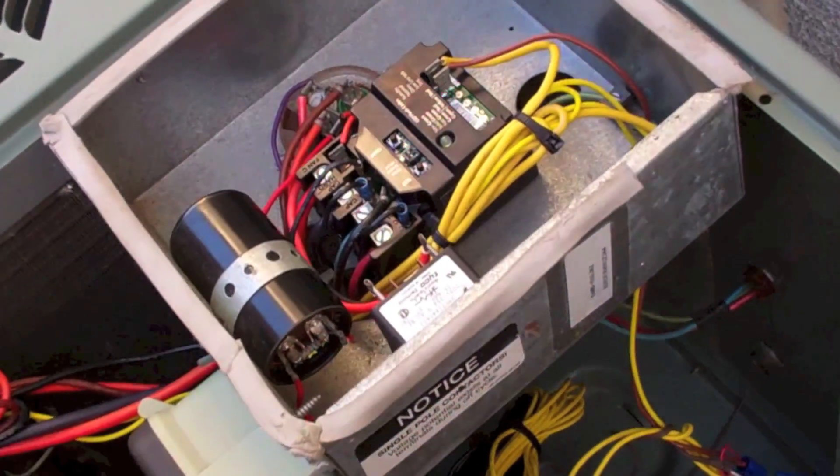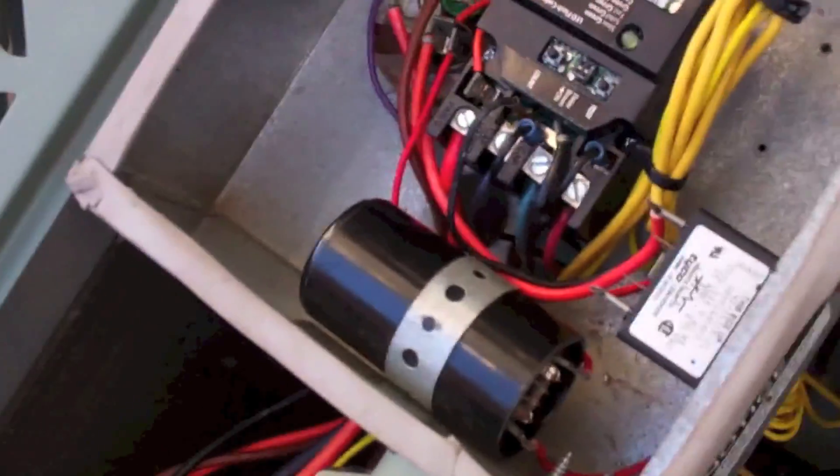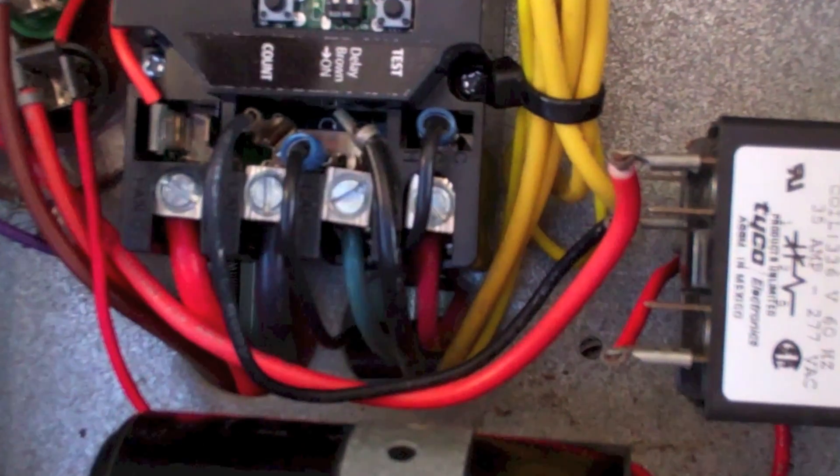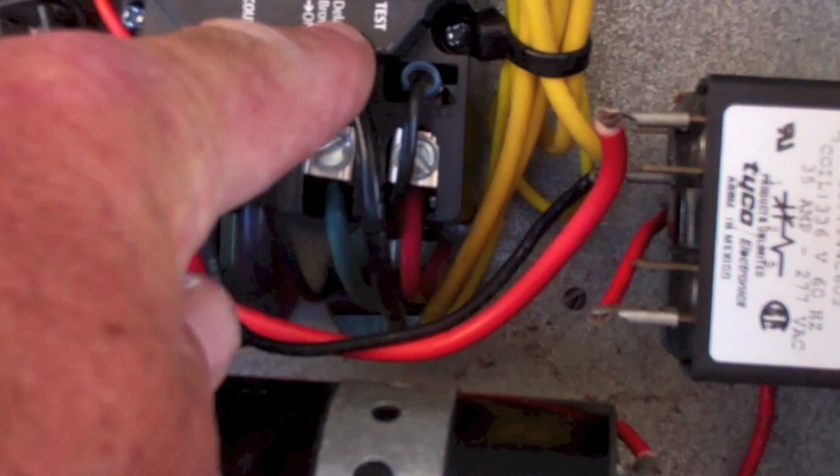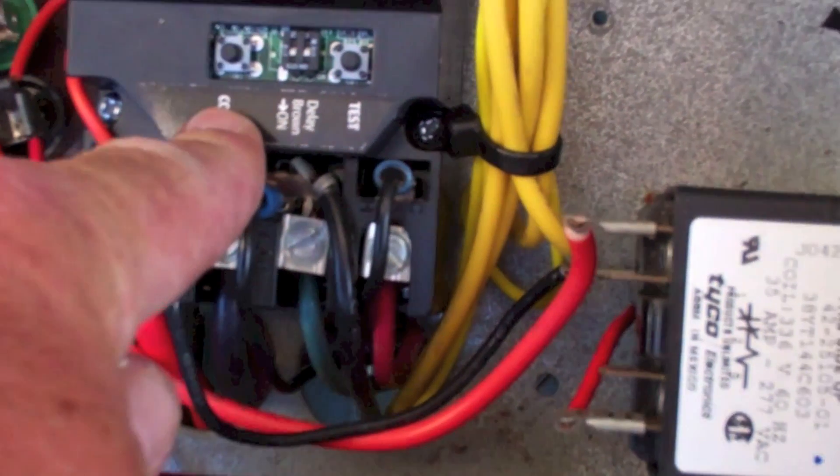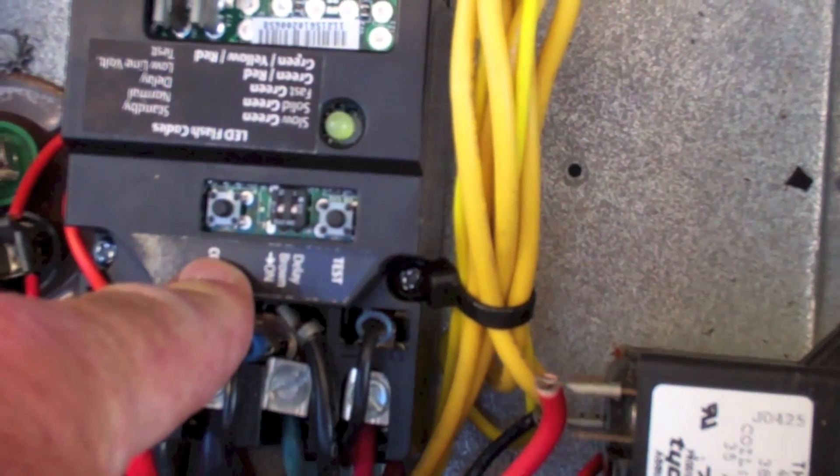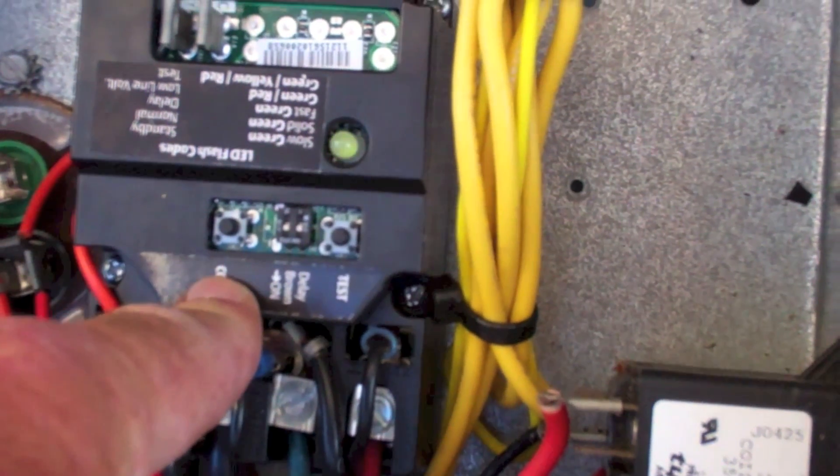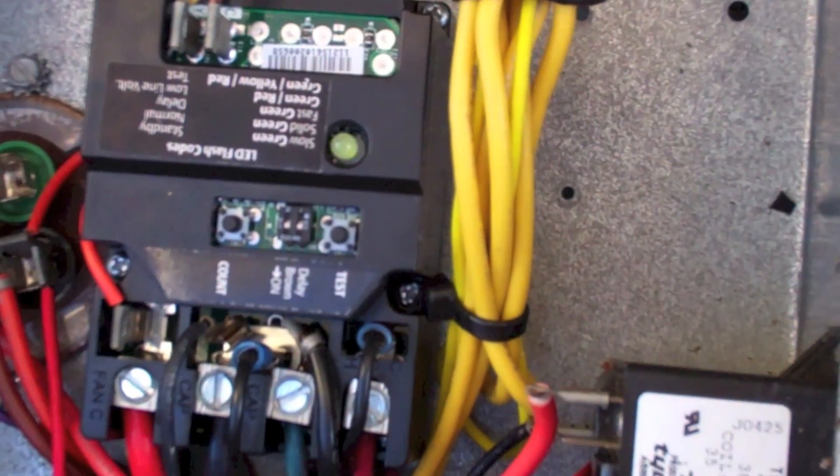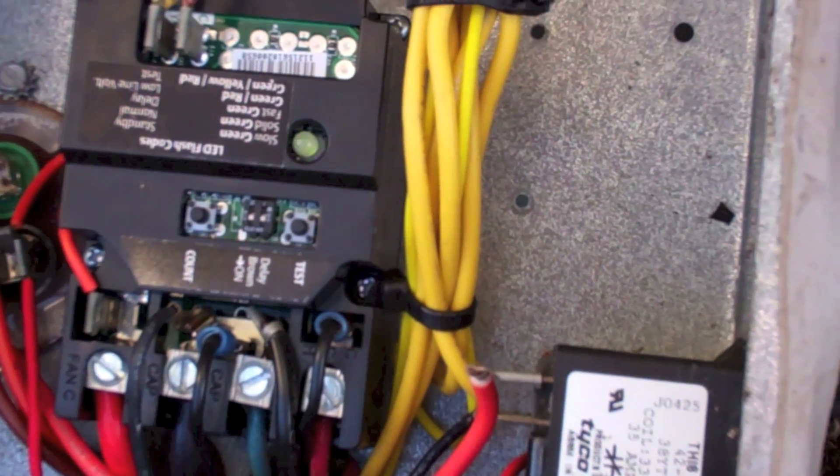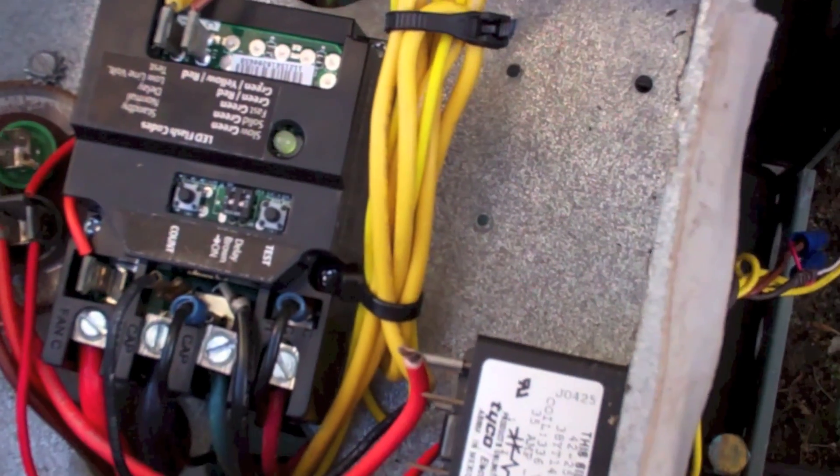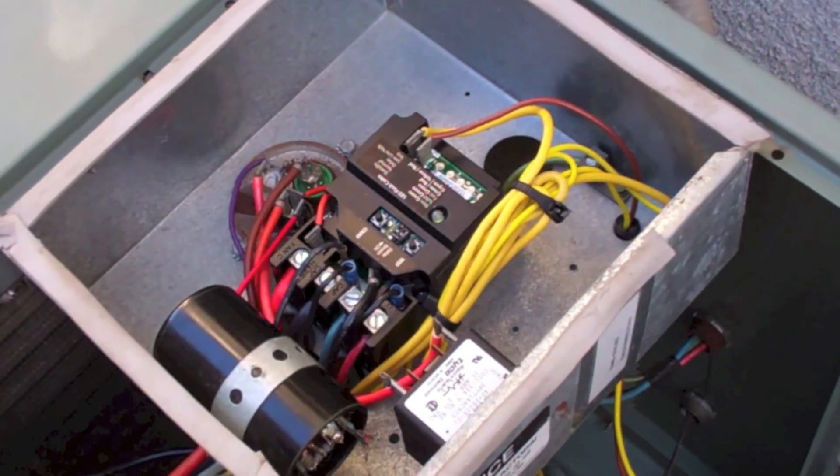Yeah, this Sure Switch is great. It's in standby, so it's gonna fire up. But it has a test button, a brownout delay, a three-minute time delay, and a count timer. So you can see how many times the contactor has been activated through its lifetime.